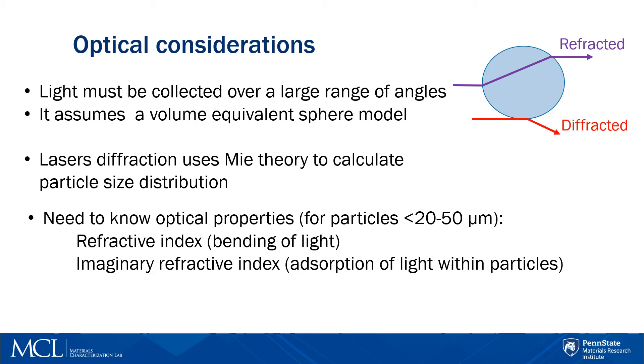Laser diffraction uses Mie theory to calculate particle size distribution by volume. Note that for particles larger than a certain size, the vast majority of light is scattered by diffraction. That certain size is determined as a multiple of the wavelength of light used for the measurement, and is typically approximated at 20–50 microns.